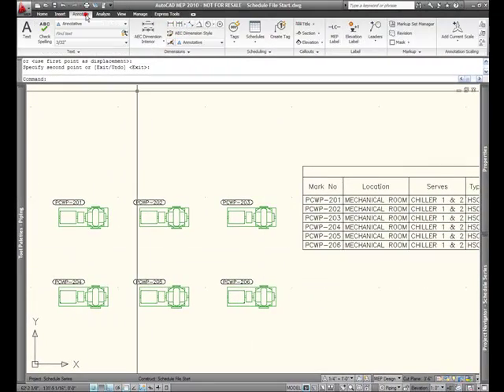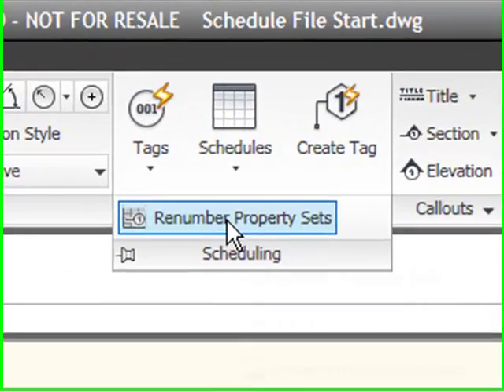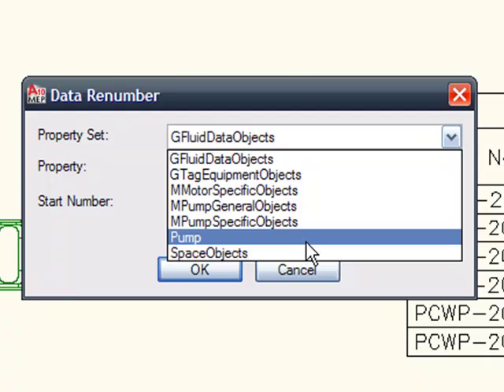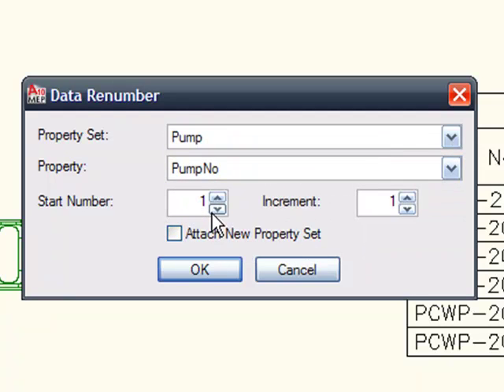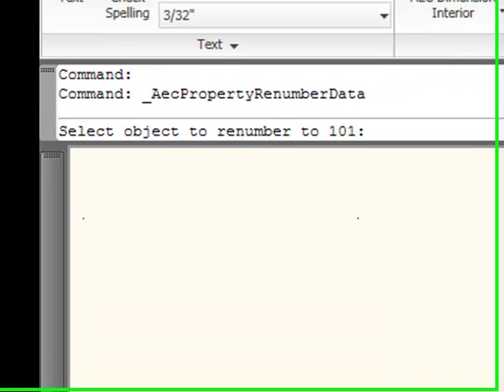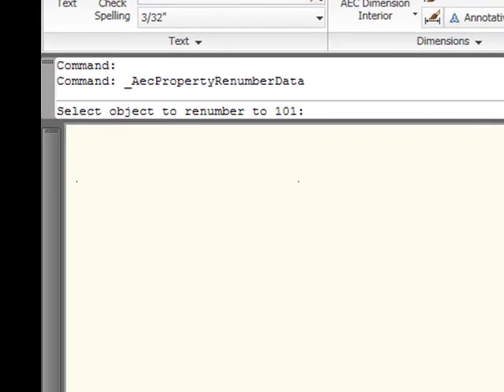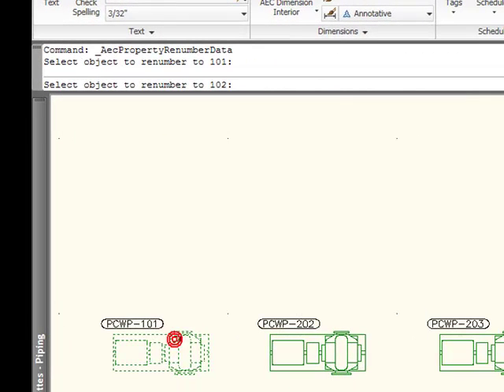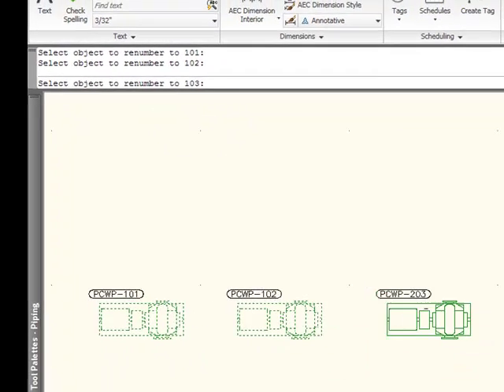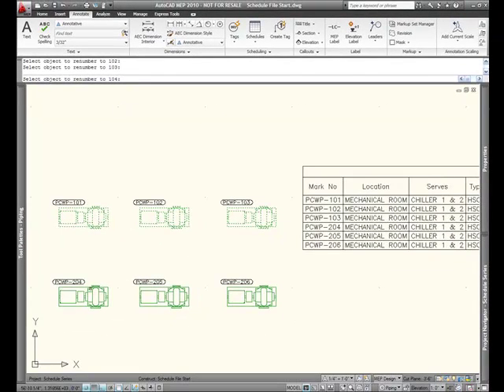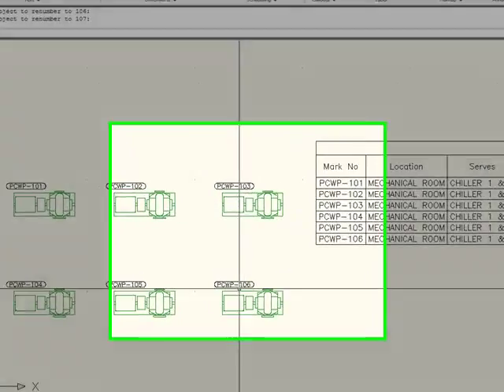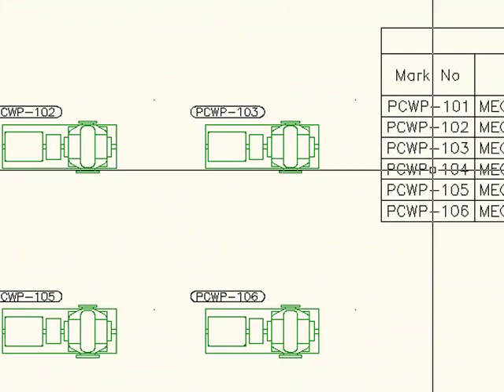Okay, so there's a couple of other things. Maybe we made a mistake and these pumps aren't on the second floor. Maybe these are on the first floor. So, we can simply tell AutoCAD MEP to start out with a pump number of 101. And up in the command prompt, it's telling me, hey, select the number you want to be 101. So, I'll select the first pump. And if I look back at the command prompt, it's now asking me to select 102. So, what I'll do here is I'll pick in the proper order that I want them in. And AutoCAD MEP automatically renumbers not just the tag, but it also affects the schedule as well.